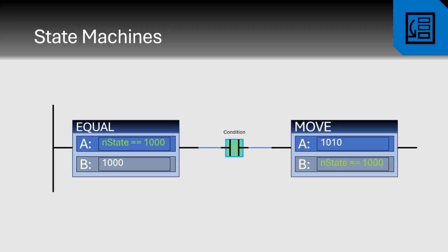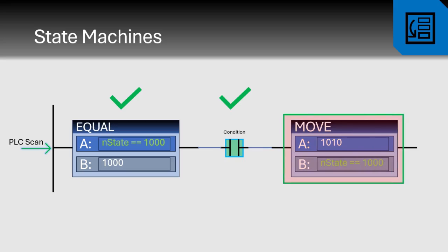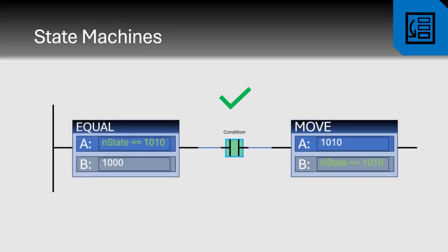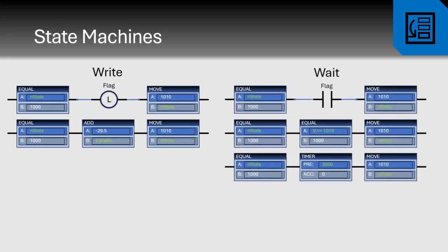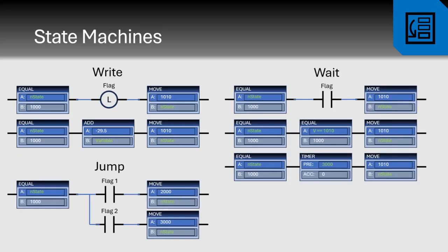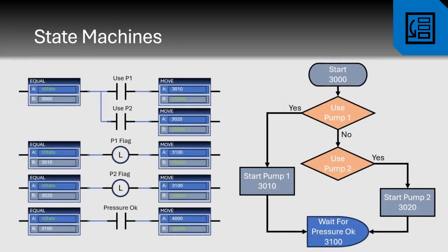When all of the conditions are satisfied, the event is completed. In other words, the detector recognizes the state, then the node verifies or initiates an action, and finally triggers the state transition. A state can write to variables, wait for or read variables, or select the appropriate subsequent state. The following example uses all three types to select which pump motor is to be used.